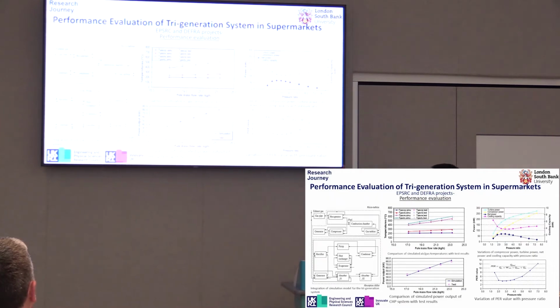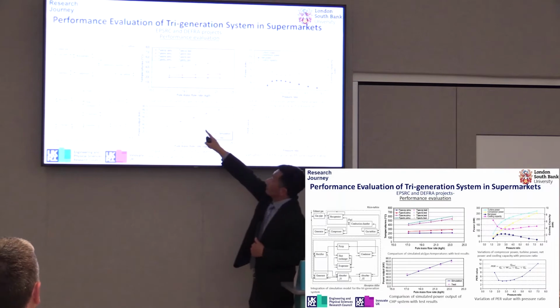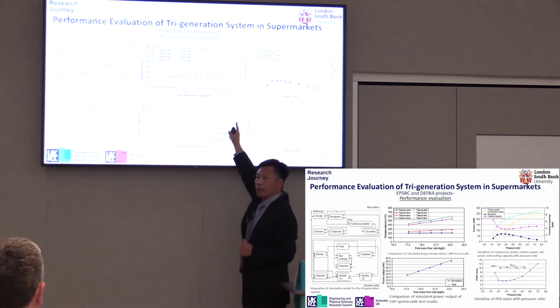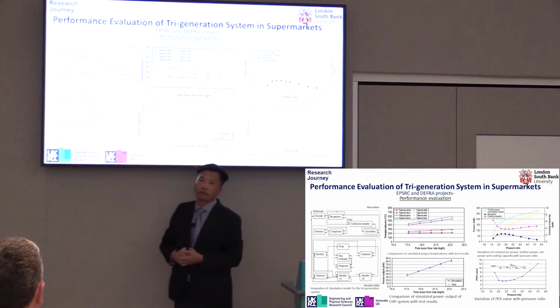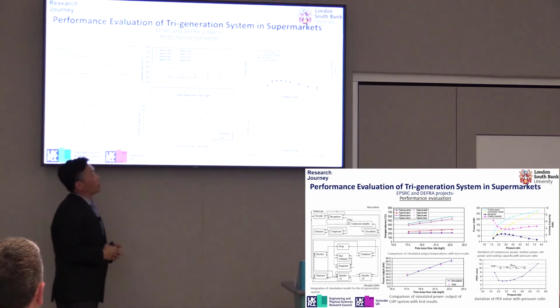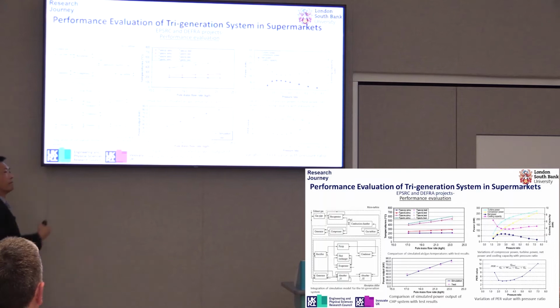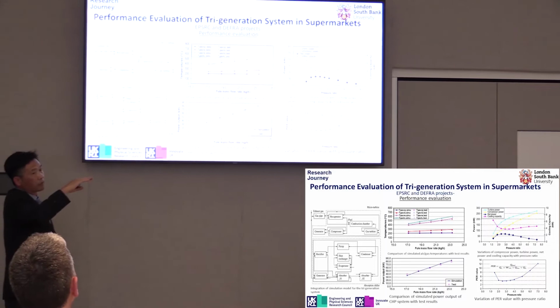From this figure you can see that when you increase the natural gas fuel mass flow rate, the temperatures at the compressor outlet, the turbine outlet, and the CHP unit outlet all increase slightly.